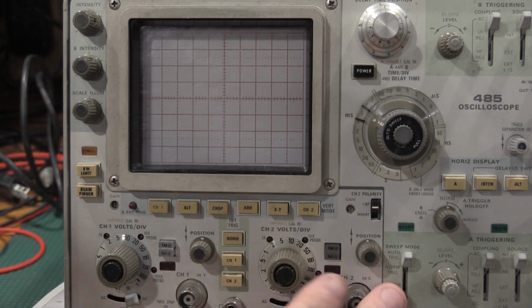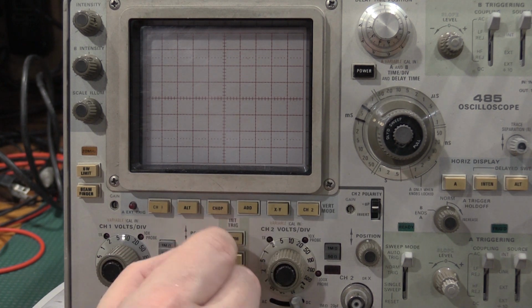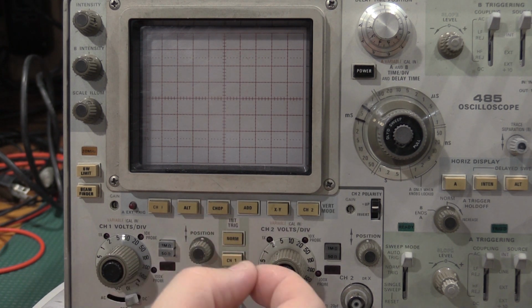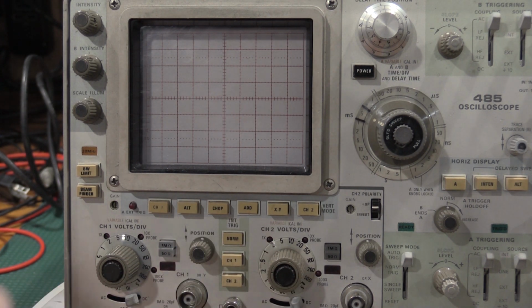Channel 2 is fine. No problems with channel 2. Channel 1's the troublemaker. So I'm going to pull this knob off, see if it's something in the knob that can just be cleaned, or if it's in the shaft. If it's in the shaft, I'll pull the attenuator out, and we'll take a look at that, see what we can do. I want this thing working perfectly so I can use it on the bench.